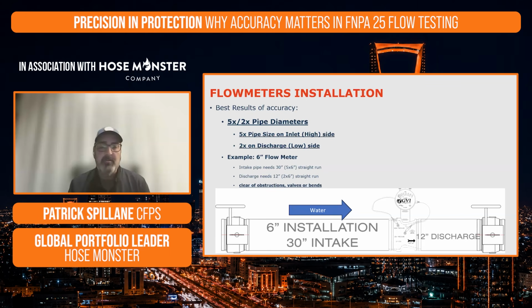I see a lot of flow meters that are installed improperly. They don't have the proper intake pipe. And when it comes to that, again, that's going to lead to an inaccurate flow test. An inaccurate flow test not only could lead to a systematic failure of your fire sprinkler system, it could also lead to unnecessary repairs. If we fail that fire pump inadvertently just because the flow meter wasn't installed properly, that could go into a very expensive repair of that fire pump that may not need to be repaired or replaced at that time. So making sure that we have that flow meter installed properly is a huge, great first step to making sure that you're doing an accurate fire pump flow test.